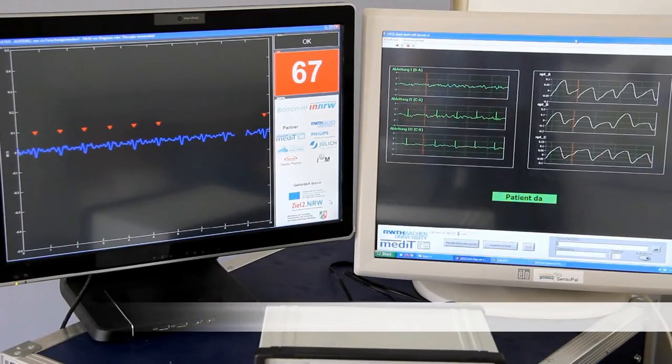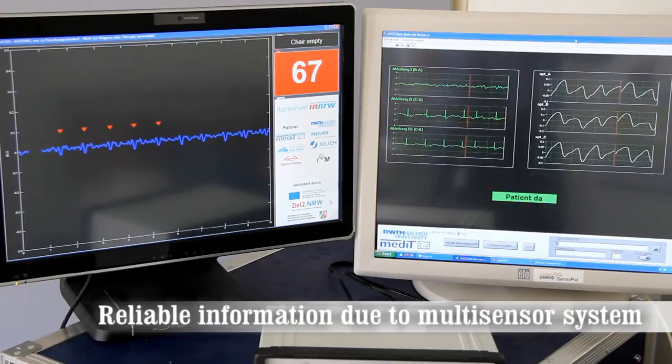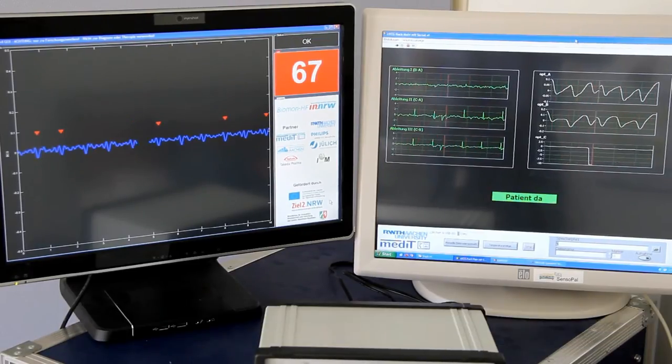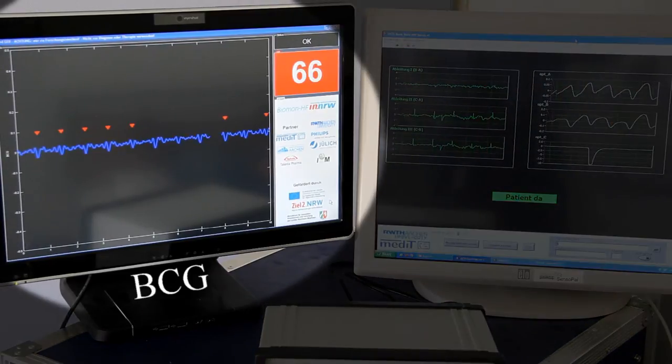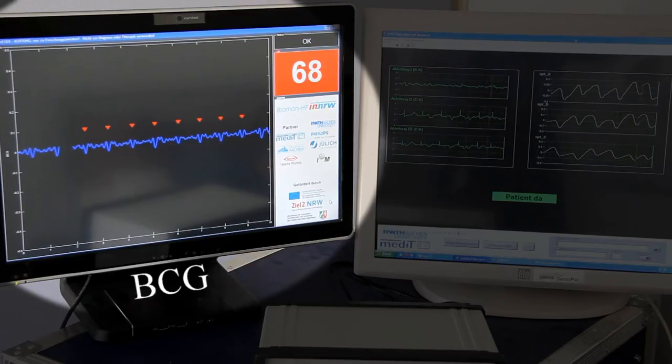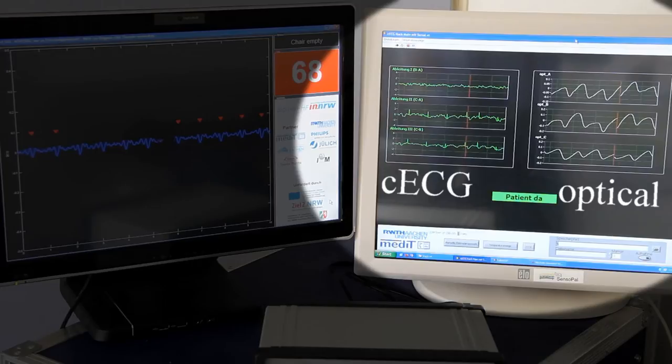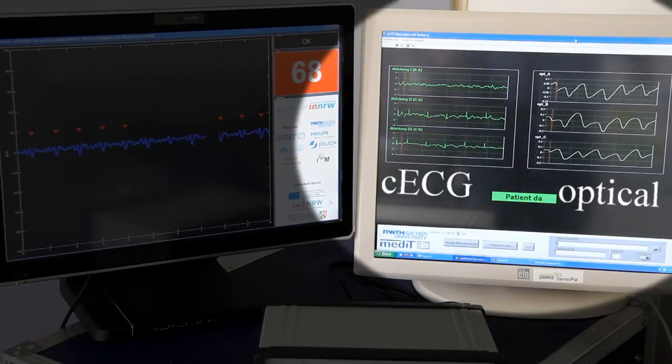In our research prototype, we utilize multiple different sensing approaches to achieve reliable and robust vital signs measurements. On the one hand, we detect the mechanical vibrations caused by the beating of the heart, the so-called ballistocardiogram or BCG. On the other hand, capacitive electrocardiogram, CECG, and optical sensors are used.